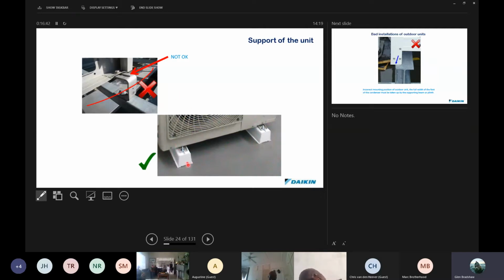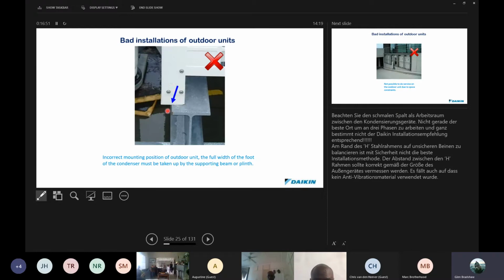It's not okay. Or on some sort of surface that takes up the full weight of the unit. Okay, considering, okay, like a plinth, okay, something like that. Over here, for instance, that's incorrect. You need a correct mounting position. Okay, the full width of the foot of the condenser must be taken up by the supporting beam or plinth. Okay, so the unit must be mounted in a way that it's stable. And you will notice in the books that it does mention that the units must be bolted down. Okay, so like I said, we have had 300 kg machines that have been blown over in the wind. And that is a sure warning that if it's happened once or twice, it can happen many times after that.